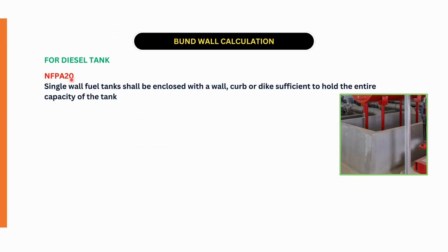NFPA 20 has only one statement related to the bund walls. As per NFPA 20, single wall fuel tanks shall be enclosed with a wall, curb, or dike sufficient to hold the entire capacity of the tank. You can observe the diagram showing the wall surrounding the diesel tank. According to NFPA 20, single wall fuel tanks must have these walls surrounding them.